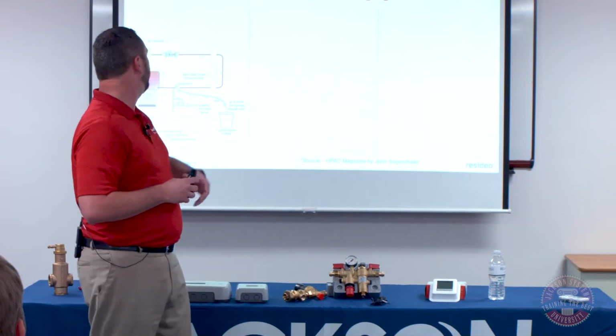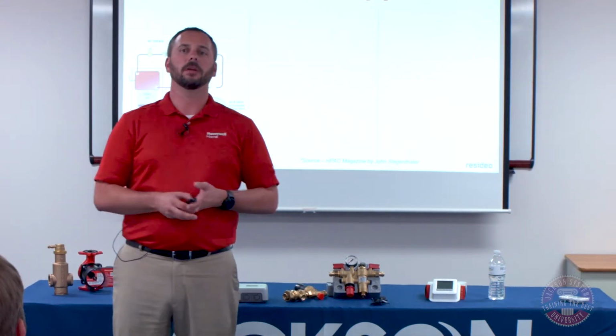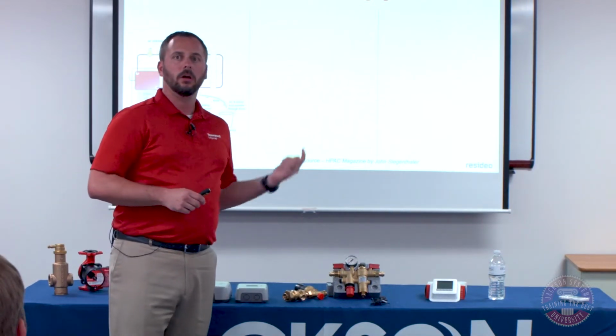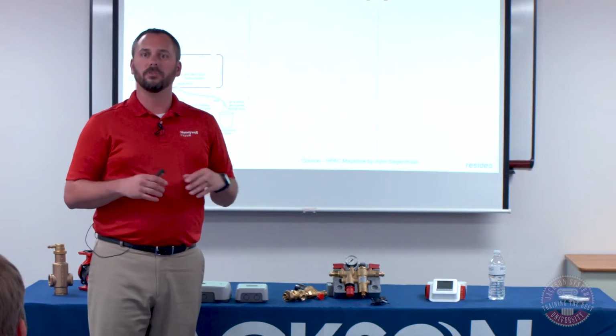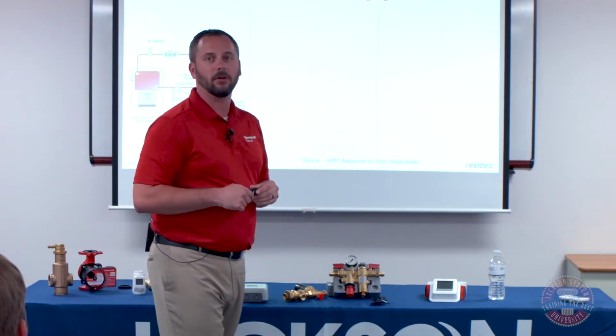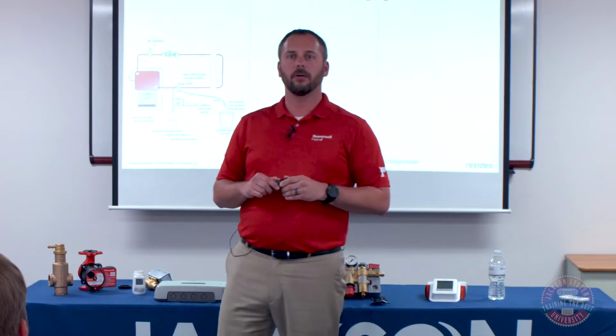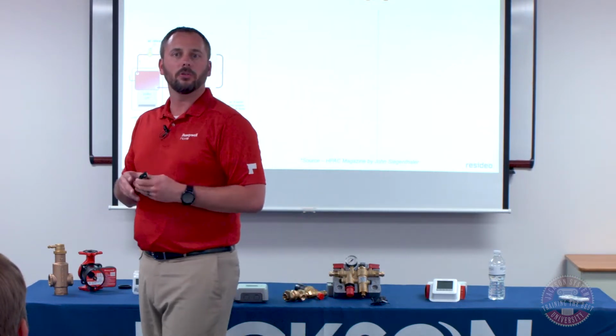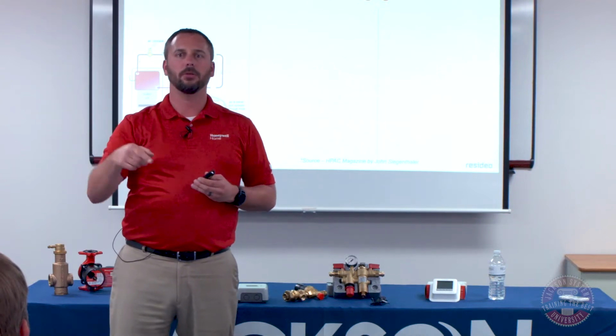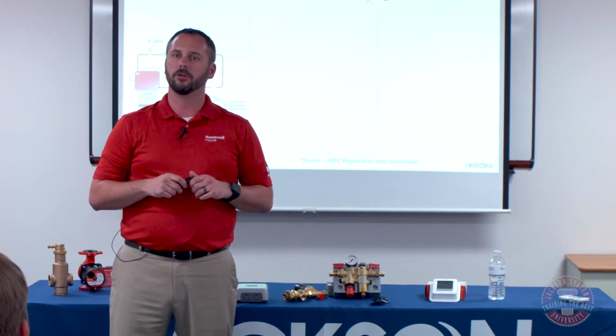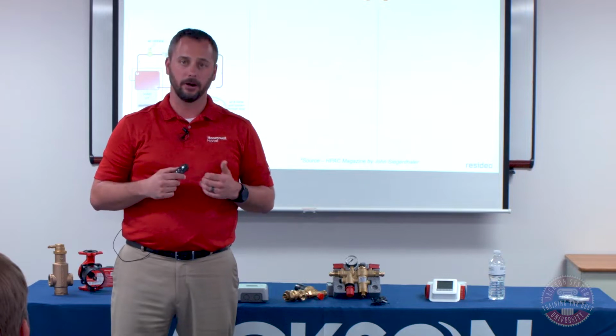That's just coming in from the city, going up into the system, kind of going left through the boiler, up around the top as if it was a one-loop system, and then it comes down into a boiler drain with a ball valve right behind it. That way you can close the ball valve, drive that water up around the system, out through the system, through a boiler drain right before it. And you're hitting 95% of the water that's in there.